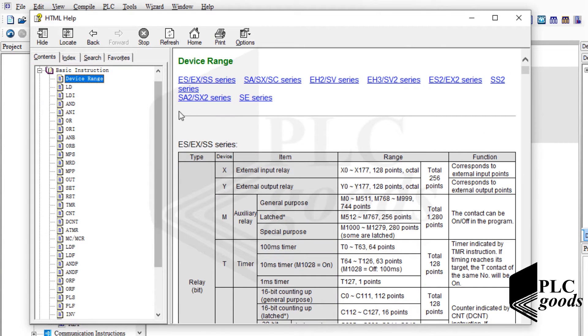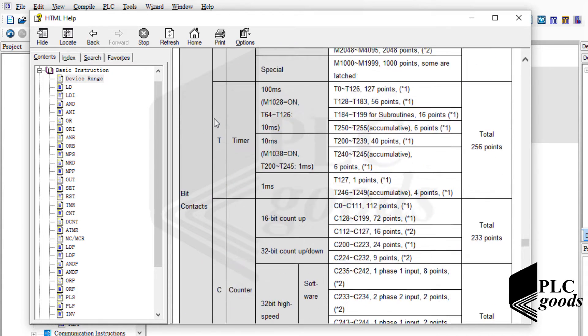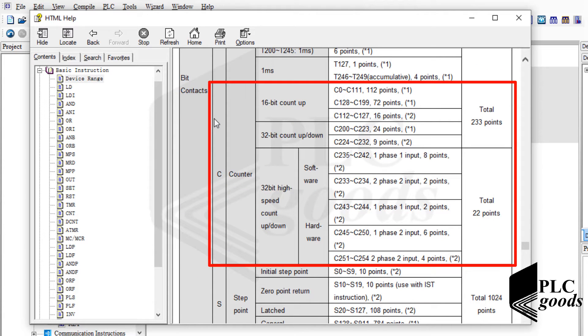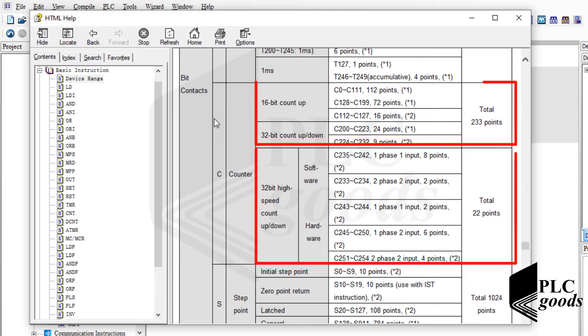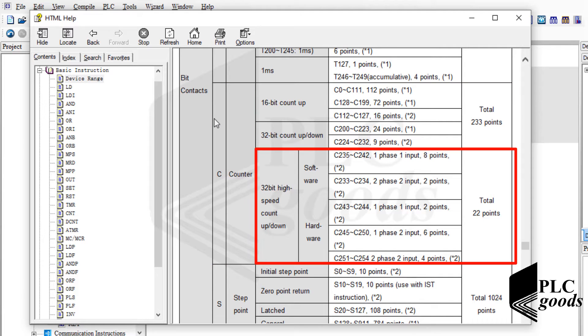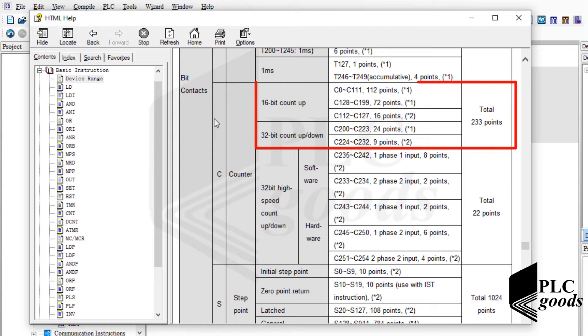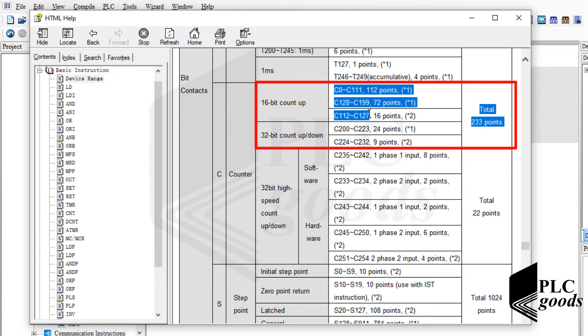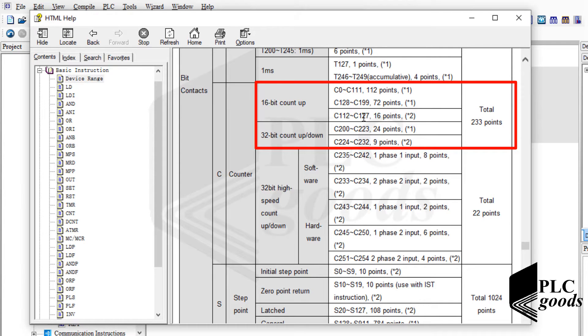Let me select my PLC type — here all available counters can be seen, which are divided into two groups: general and high-speed counters. The first group includes 16-bit and 32-bit counters for general purposes. Note that 16-bit counters starting from C0 to C199 are up counters only, while 32-bit counters can count more events and can be used for counting both up and down.